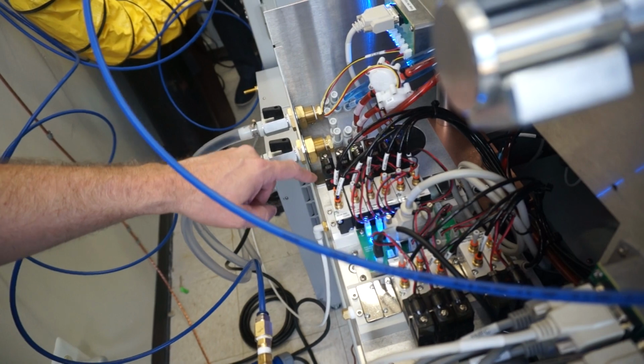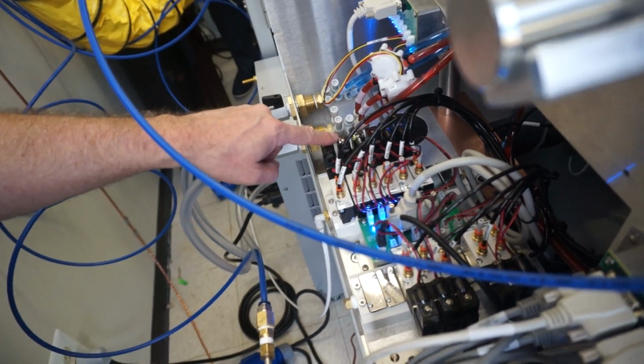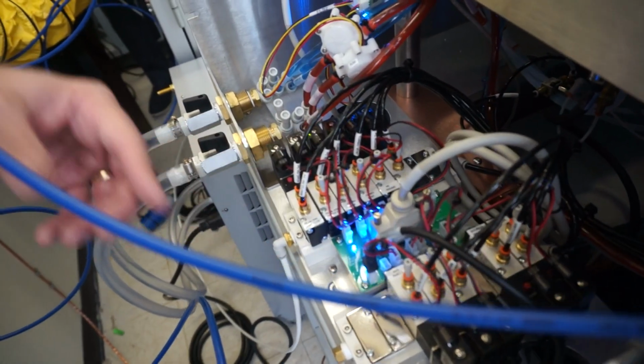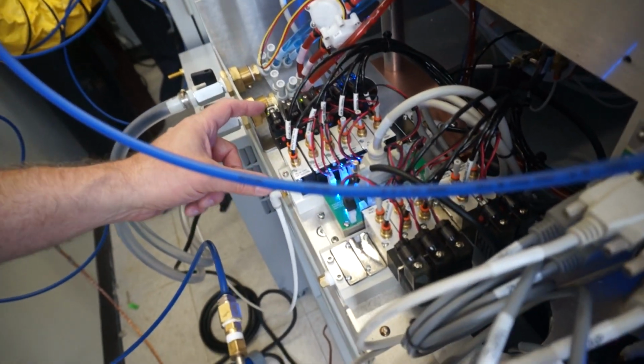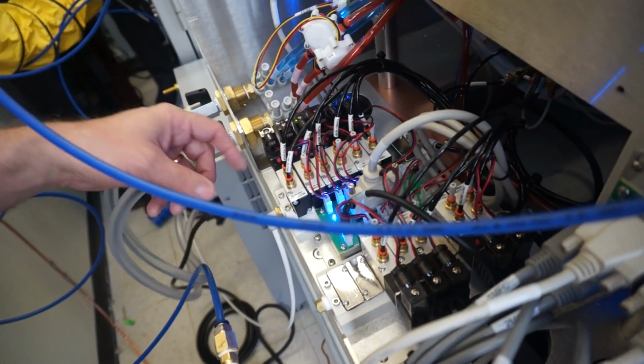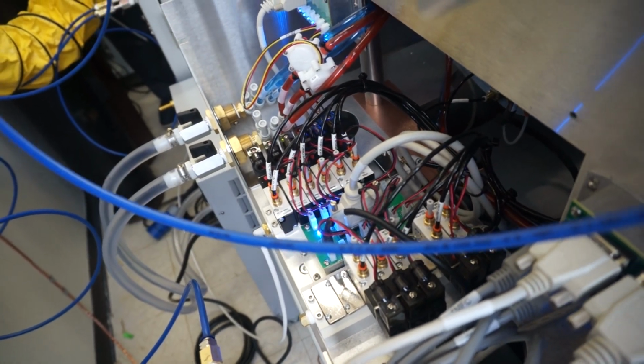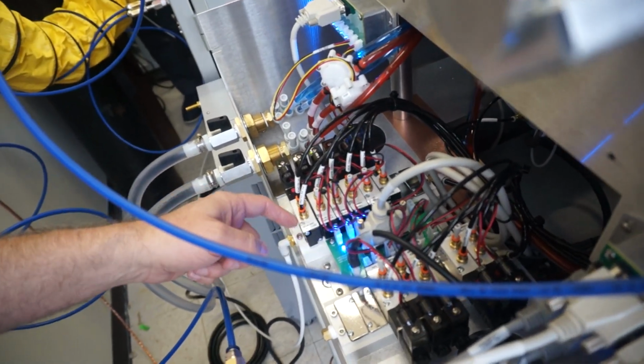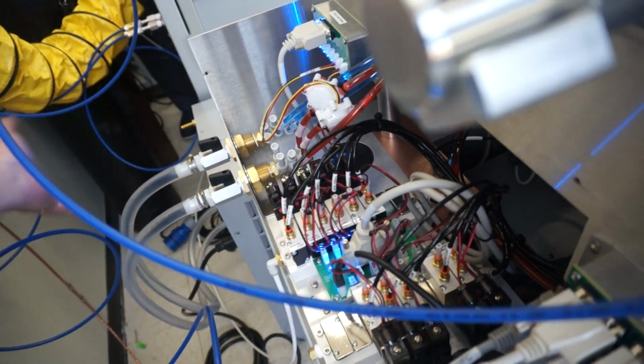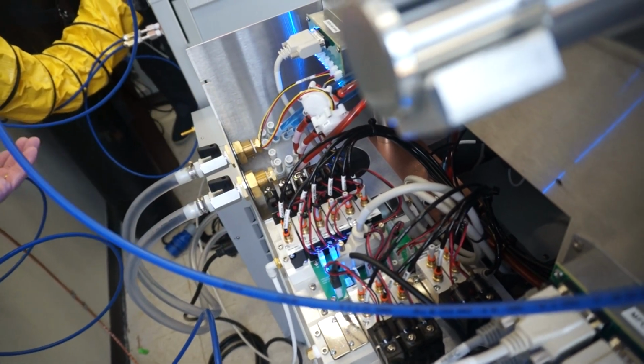And these solenoids, if they're on or active, you'll see there's an LED. It's lit up. It's on. Whenever there's no power, these are a single detent solenoid. So when it's energized, it's going to move a spool within. It's going to permit air to travel to that component. When you de-energize it, it's basically a spring return, which will close it off. So really simple to troubleshoot.